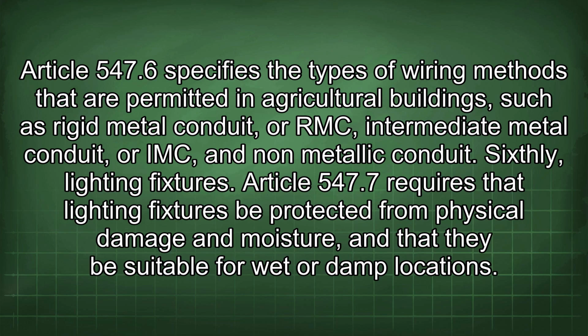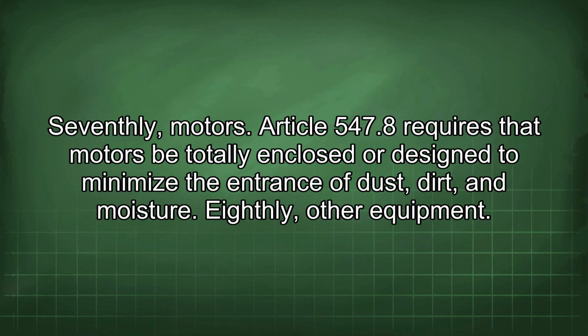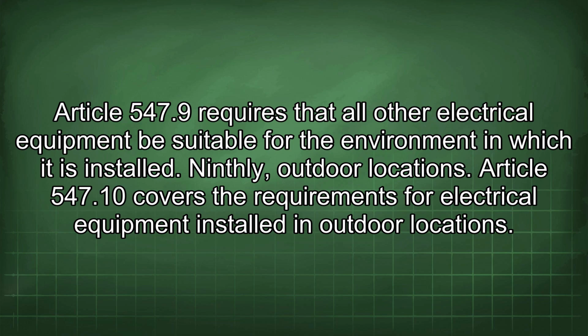Sixthly, lighting fixtures. Article 547.7 requires that lighting fixtures be protected from physical damage and moisture, and that they be suitable for wet or damp locations. Seventhly, motors. Article 547.8 requires that motors be totally enclosed or designed to minimize the entrance of dust, dirt, and moisture. Eighthly, other equipment. Article 547.9 requires that all other electrical equipment be suitable for the environment in which it is installed. Ninthly, outdoor locations. Article 547.10 covers the requirements for electrical equipment installed in outdoor locations.